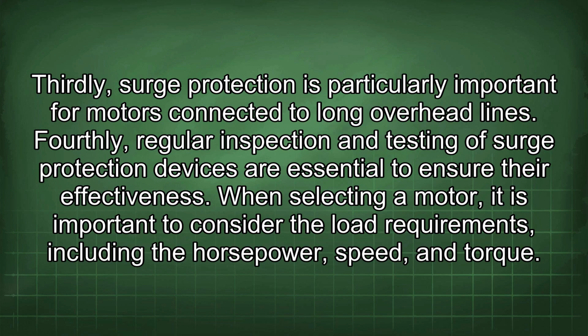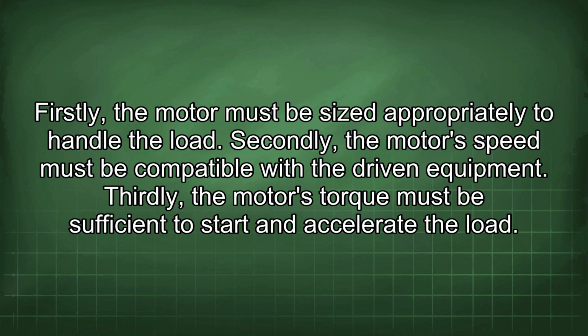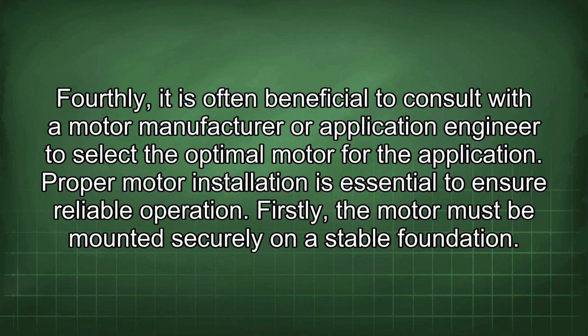When selecting a motor, it is important to consider the load requirements, including the horsepower, speed, and torque. Firstly, the motor must be sized appropriately to handle the load. Secondly, the motor's speed must be compatible with the driven equipment. Thirdly, the motor's torque must be sufficient to start and accelerate the load. Fourthly, it is often beneficial to consult with a motor manufacturer or application engineer to select the optimal motor for the application.